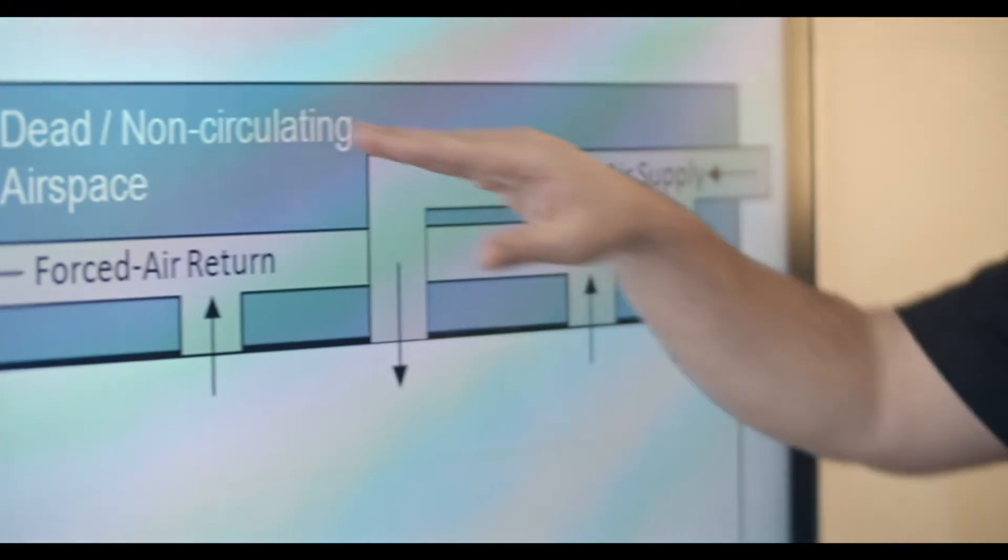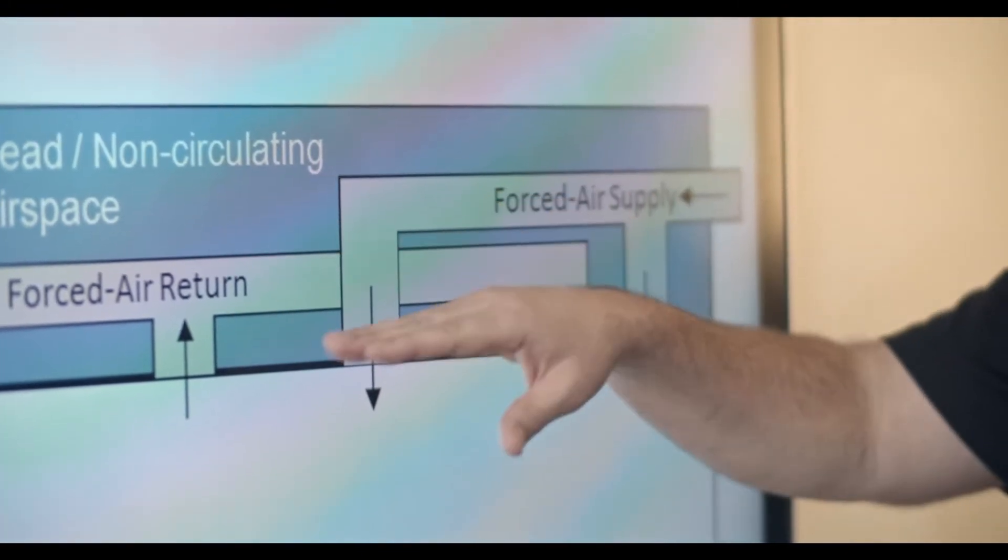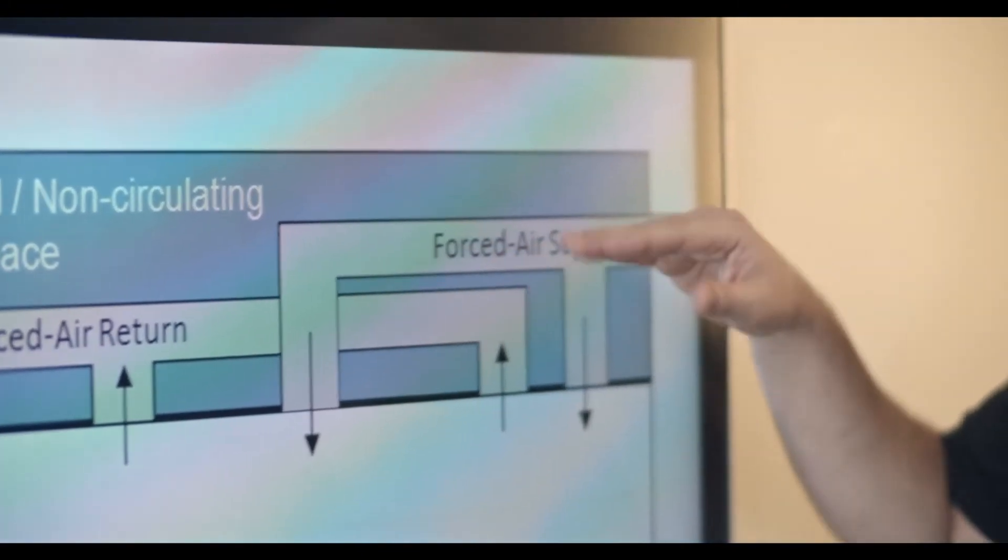And so that space above the ceiling then when I've got duct work in place, it has both a forced air in and a forced air out using duct work, then that is a non-plenum environment. In that case I can use non-plenum cabling up here in this open spaced area above the work area.